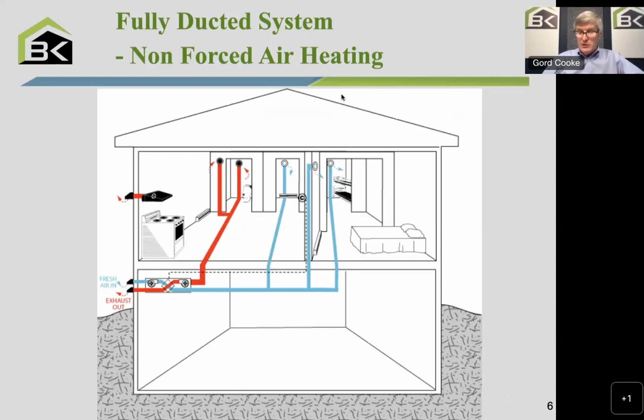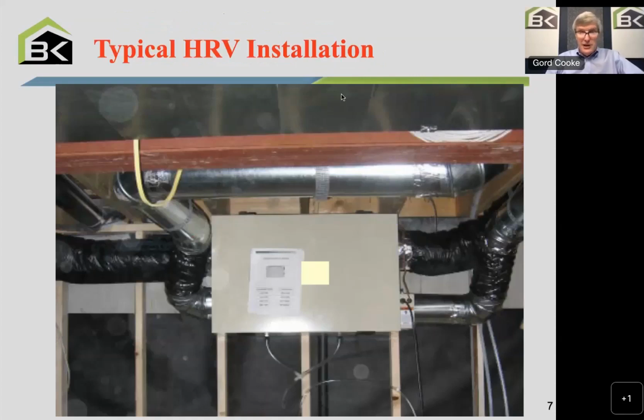So 2 typical installation types. And there's a unit installed in a house. You'll see it hung in this case in the basement off the floor joist system. You'll see those 4 ducts, one from the right-hand side, exhaust air being taken out of the building and sent to the outside. That's that insulated duct. On the left-hand side, you'll see that black insulated duct. That's bringing in air from outside. So 2 insulated ducts that we need to think about, 1 bringing air in, 1 taking air out, and then the ductwork, the exhaust from the bathrooms and the kitchen, and the fresh air either to the furnace return or to each individual bedroom. So that's a fairly typical installation.